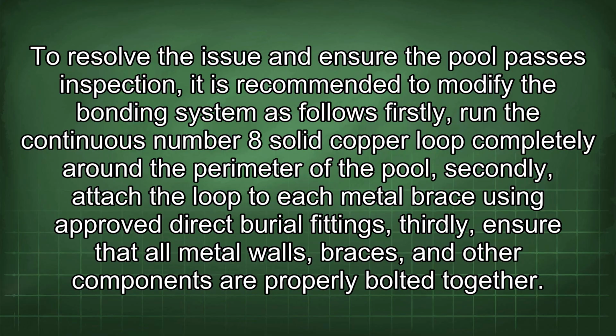Firstly, run the continuous number 8 solid copper loop completely around the perimeter of the pool. Secondly, attach the loop to each metal brace using approved direct burial fittings. Thirdly, ensure that all metal walls, braces, and other components are properly bolted together.